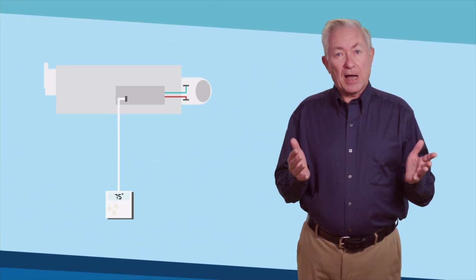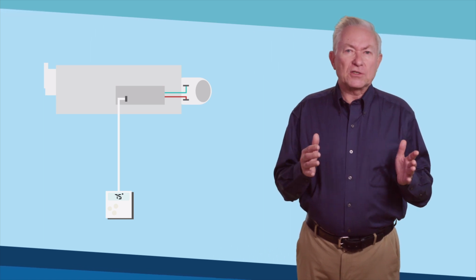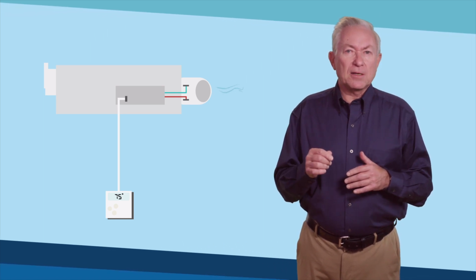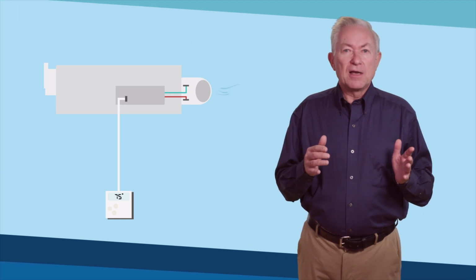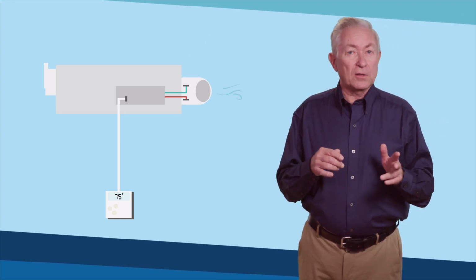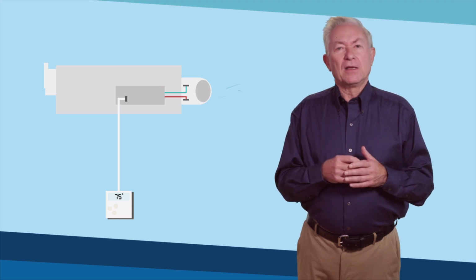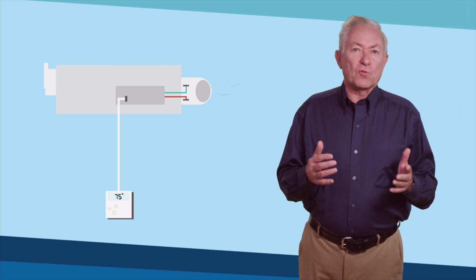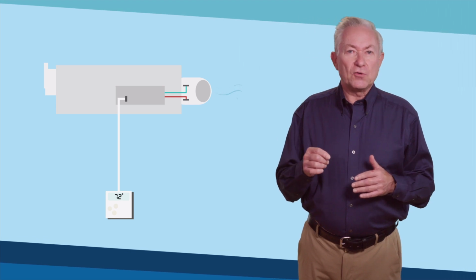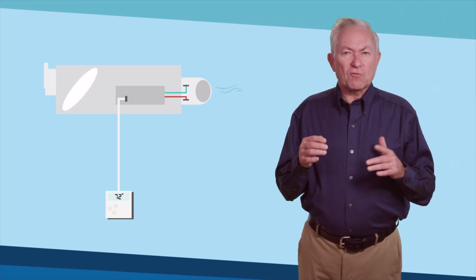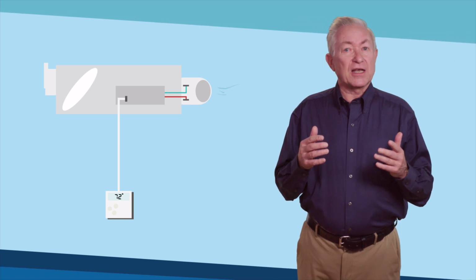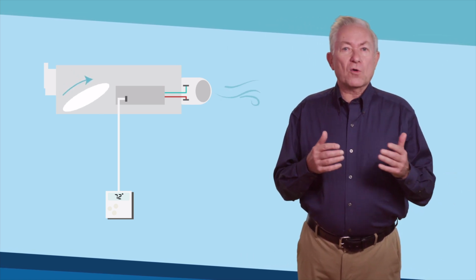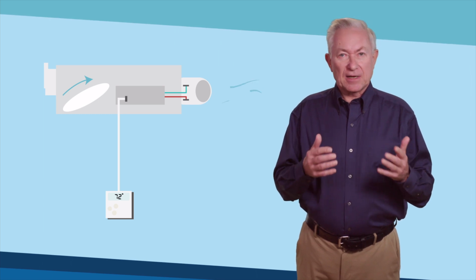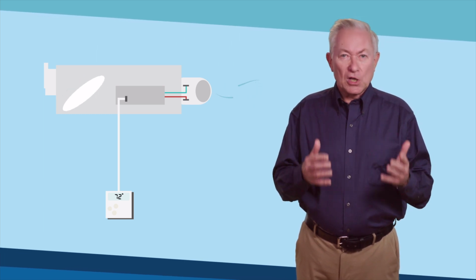Each room that contains a thermostat has a box above the ceiling known as an air terminal box. In newer air terminal boxes, we can control airflow and sometimes temperatures for more critical areas by reheating the air if it is too cold or cooling it down if it's too hot. For instance, if it's 75 degrees in a room and you turn the thermostat down to 72, the damper for the box, which is a regulating device that controls how much air is entering the room, will open. More cool air will enter the room until the temperature is 72, and then the damper will close again.